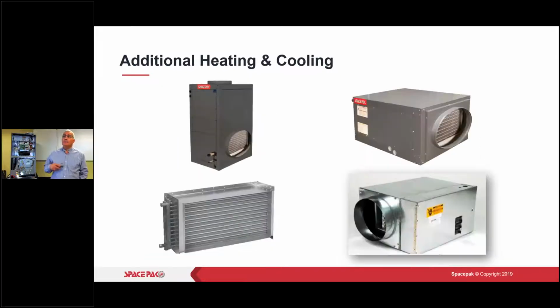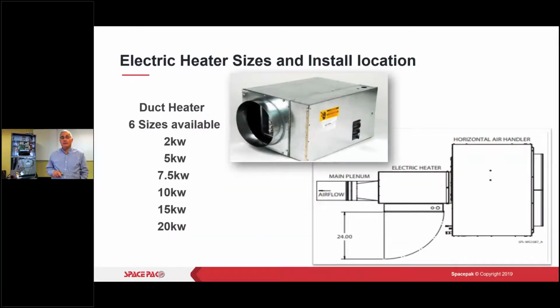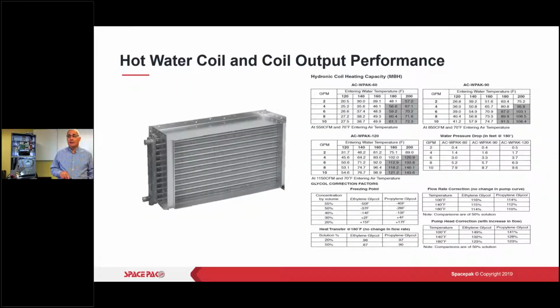If you need to bump up or add heating to our product, we can do it with either a hydronic coil or electrical coils. We have duct heaters available for you, as you can see here in those 6 sizes: 2 kW, 5, 7.5, 10, 15, and 20 kW, if you want to go with electric. It's more popular around these parts where we use the hydronic coil.